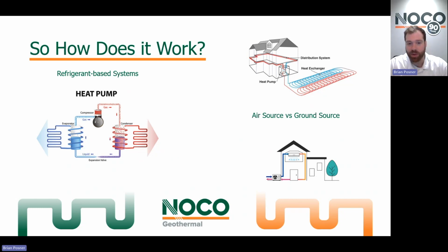A lot of people are familiar with this. The most basic example is an air conditioning unit sitting outside of your house. That is a heat pump that can only do cooling. So air source heat pumps that can do heating and cooling have a reversing valve, and they're able to run the process in reverse. So instead of pumping heat out of the home, they can pump heat into the home. Now, these systems use an outdoor fan unit as the heat sink, exchanging heat with outside air.